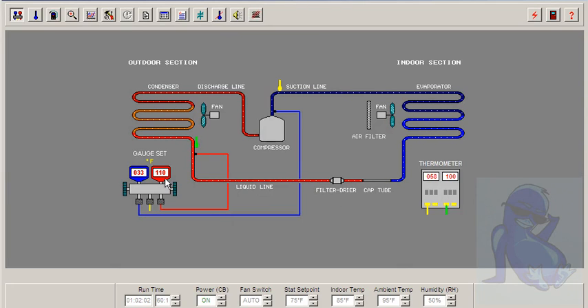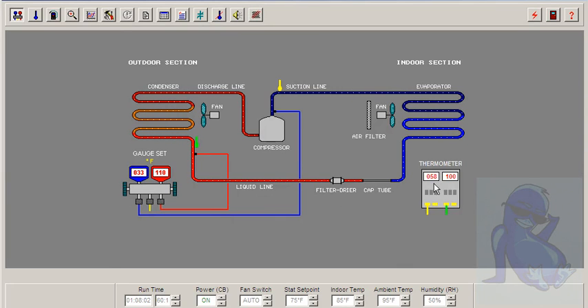Our subcooling is only 10 degrees. Our superheat is quite high. What is that, 25 degrees? High superheat.